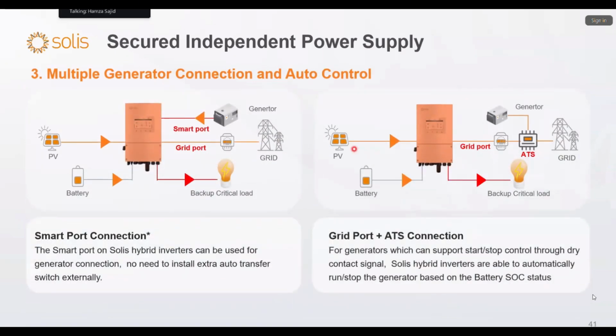Let's suppose you have multiple sources available and you want to control them. In the first scenario, we have a generator directly connected to the gen port. The inverter will automatically turn the system on and off according to the requirement. In the second scenario, the generator size is big, or the generator is already installed at the grid side. In that case, you can use an ATS that communicates with the inverter, so the inverter can still turn the generator on or off through the ATS. So these two scenarios can be easily controlled with the help of this hybrid inverter.